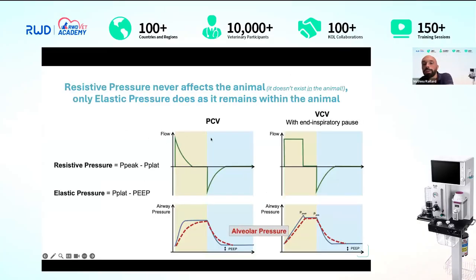See, I'm going to take the case of pressure control ventilation. I tell the ventilator that I want a given pressure in the airway throughout inspiration, and it will start a little bit slower and then will maintain that pressure over the time of inspiration. If I increase the resistance, I will still have the same pressure.